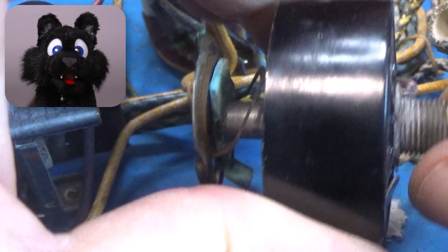The potentiometers needed cleaning too. There's one that adjusts the expected test current for the readout, labeled C control, and two that calibrate the device on the inside. All of them were oxidized and had dead spots. Took lots of careful cleaning to get them working smooth again. The power potentiometer for the primary adjustment was okay, so I just cleaned and greased the shaft.